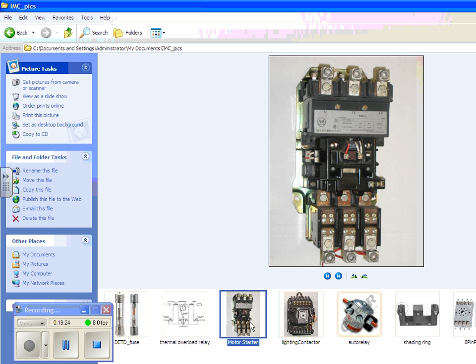So what identifies a motor starter from everything else is it not only has a holding contact, but it also has overloads. And if you're going to do a motor setup, include a motor starter with a heater, because if you don't and it burns up, it's all your fault.